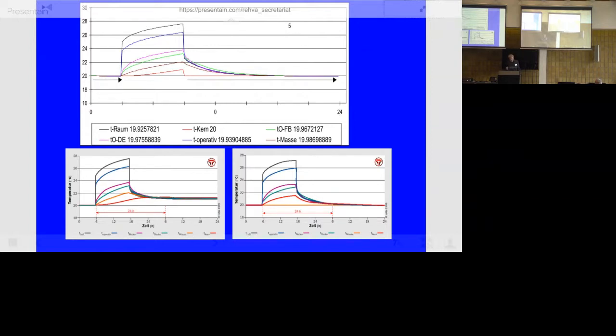Then we said, okay, if we now circulate in the middle, keeping that at 20 degrees, we see a little lower temperature during the day, but the next morning we're back at 20 degrees. So it's possible to remove it by circulating water in the slab.